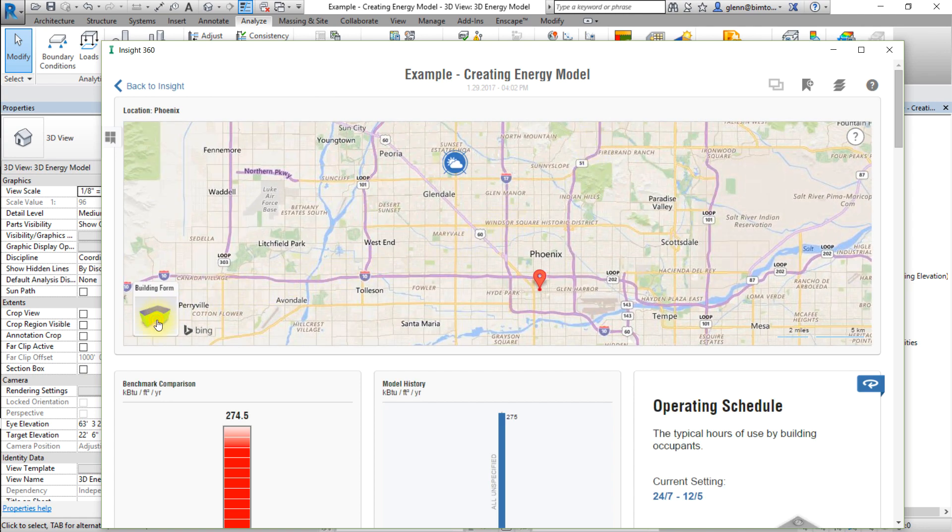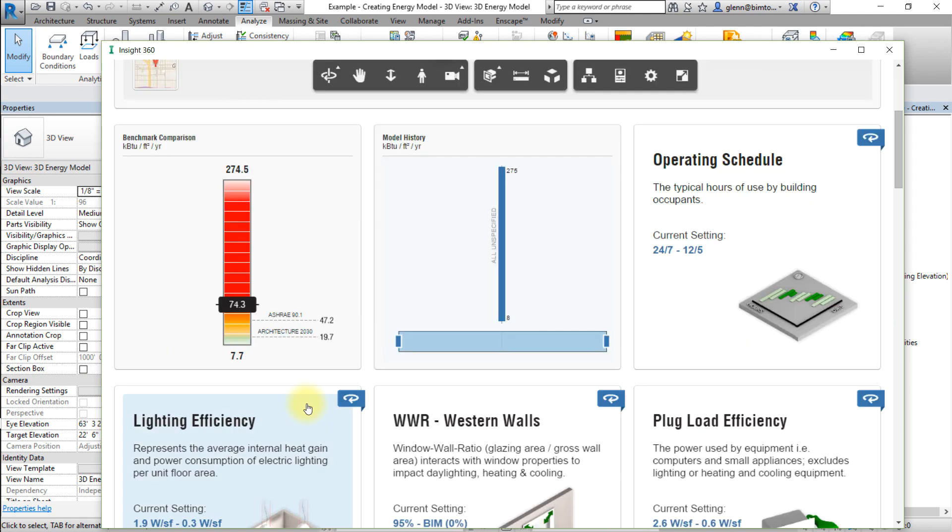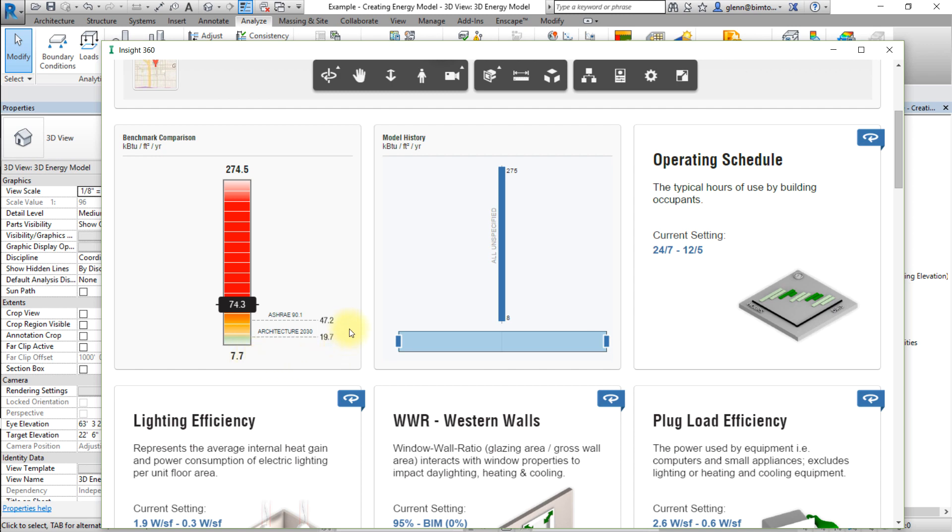The benchmark comparison displays the mean annual cost or mean EUI depending on your settings, as well as the range of potential values given your assumptions in the model. It also shows how your design's current performance stacks up against industry benchmarks such as ASHRAE 90.1 and Architecture 2030 targets for this kind of project.